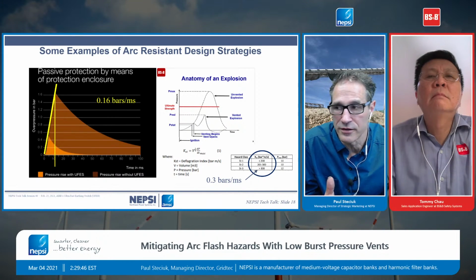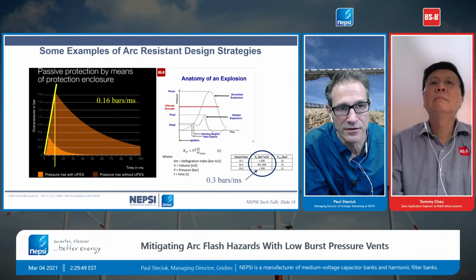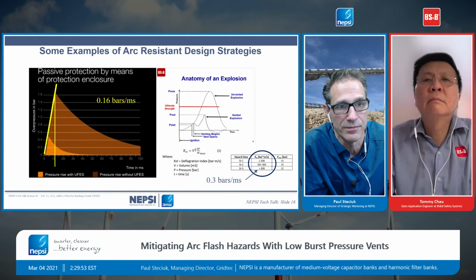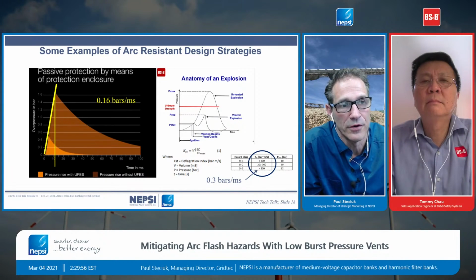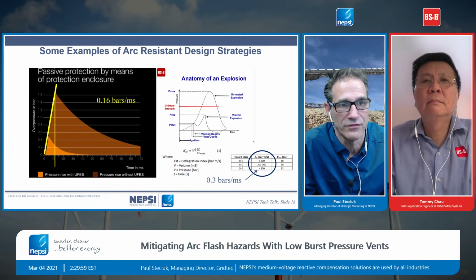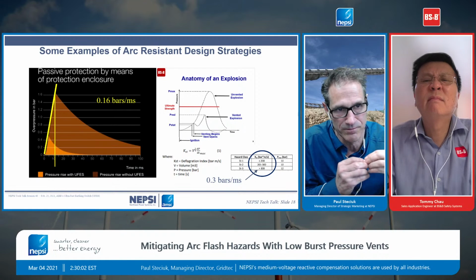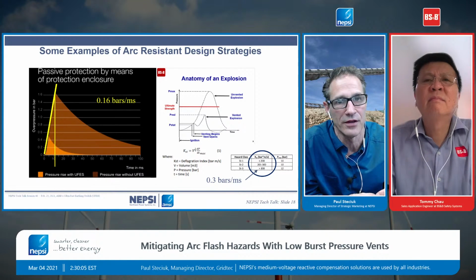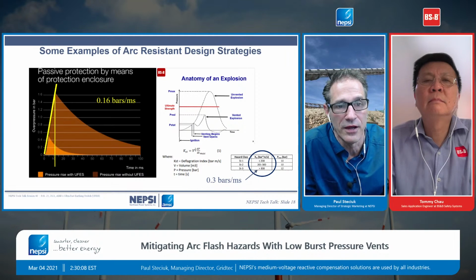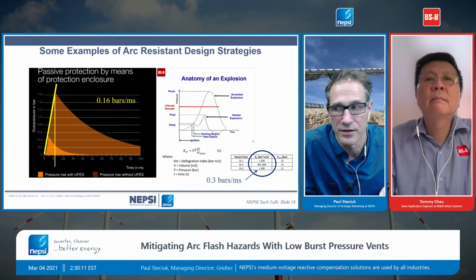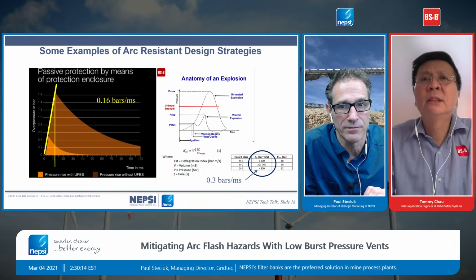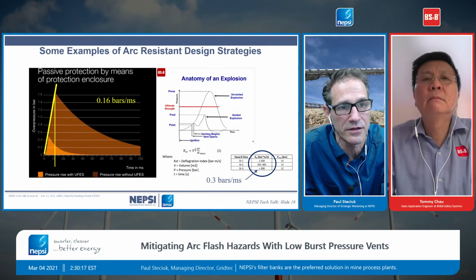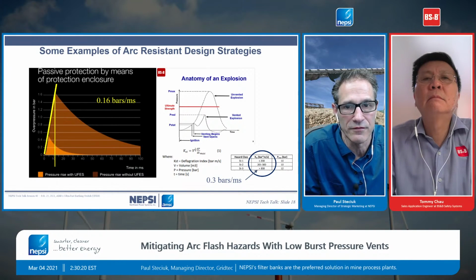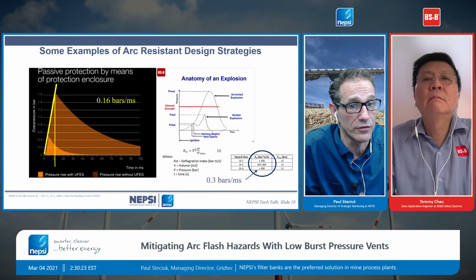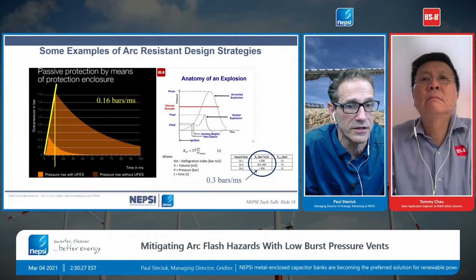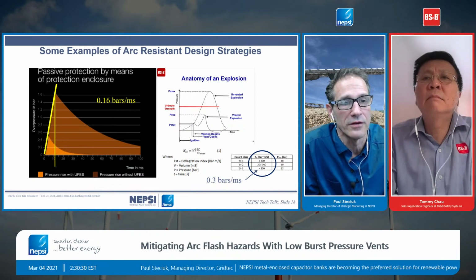So when NEPSI was looking at this, we asked: does this make sense? Does this technology make sense? Are we talking about pressure buildups that are on par with an arc flash event? Arc flash events are very fast, and in that first video the door gets blown off, so can a dust explosion do the same? I think the answer is yes, because we're showing here the pressure buildup versus time for a test done on a piece of switchgear. You can see from that video that it was 0.16 bars per millisecond, versus the dust values used by NFPA 68, which are on the order of about 0.3 bars per millisecond.